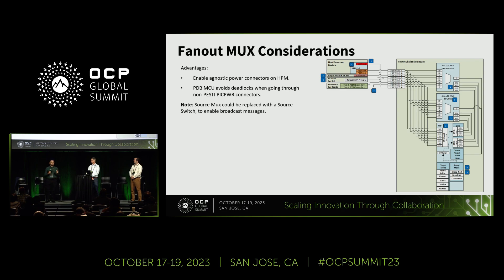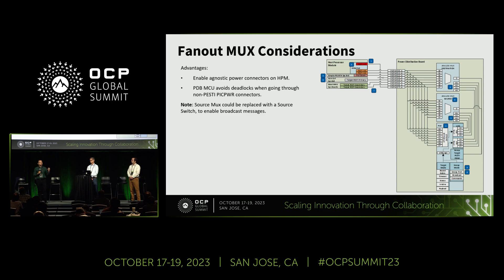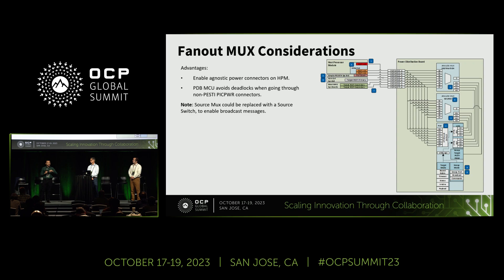You could also have a system board that doesn't have MXIO — a typical example being a fan board — where the only path to pass PESTI communication is through the MPIC connector, representing another kind of corner case. Finally, you could detect and identify system boards with only partial PESTI capabilities, where you rely on MXIO communication for transactions and use the MPIC power connector just for cable inventory. You just need to pay attention to a couple of scenarios — you don't want a deadlock between target-to-target. This is just one example of how this hyper-flexibility and agnosticity can get quite messy.